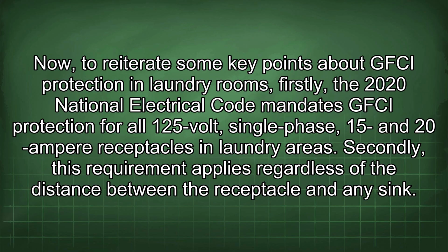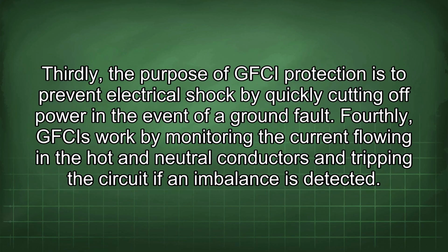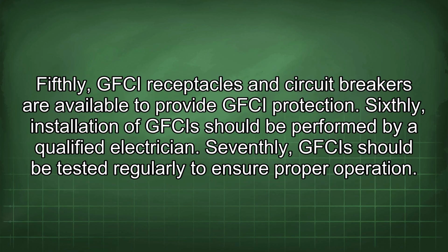Firstly, the 2020 National Electrical Code mandates GFCI protection for all 125-volt single-phase, 15 and 20 ampere receptacles in laundry areas. Secondly, this requirement applies regardless of the distance between the receptacle and any sink. Thirdly, the purpose of GFCI protection is to prevent electrical shock by quickly cutting off power in the event of a ground fault. Fourthly, GFCIs work by monitoring the current flowing in the hot and neutral conductors and tripping the circuit if an imbalance is detected.